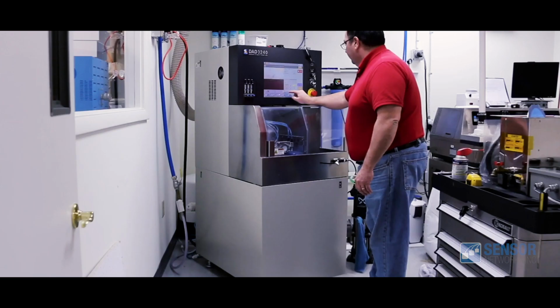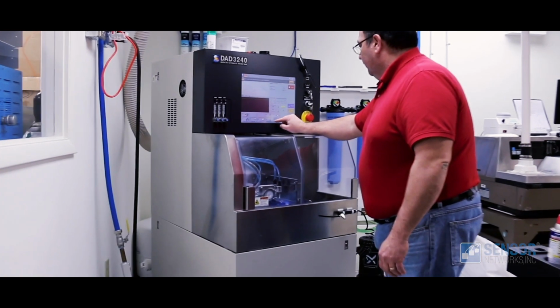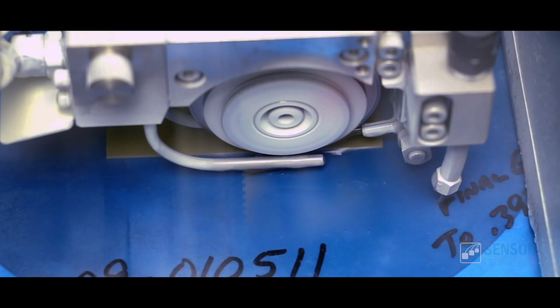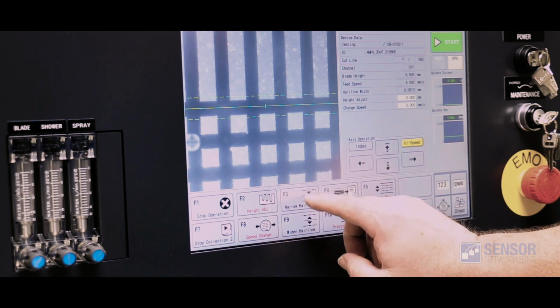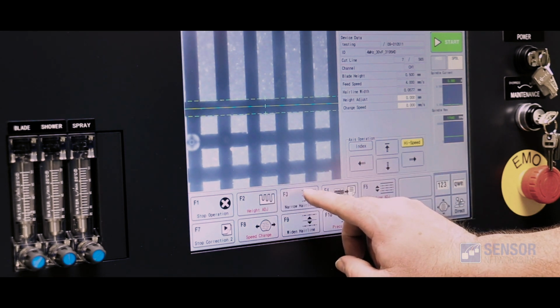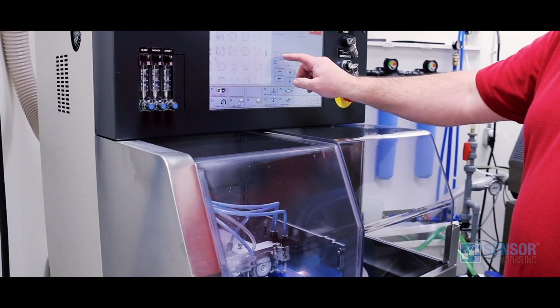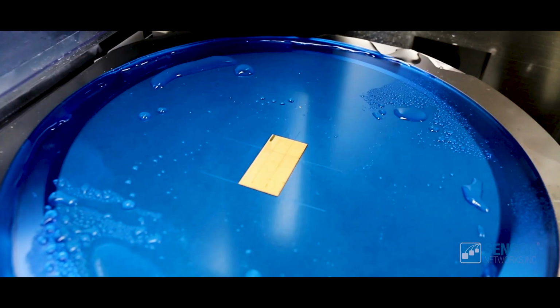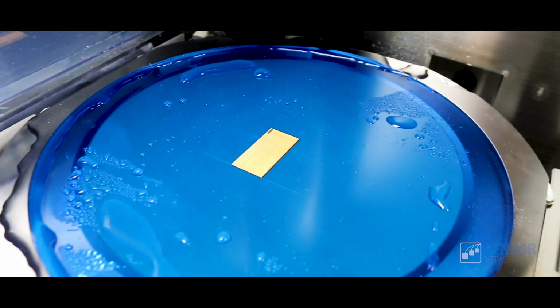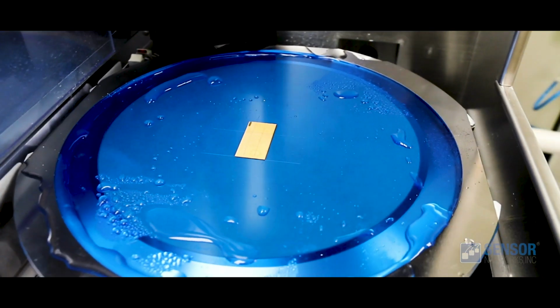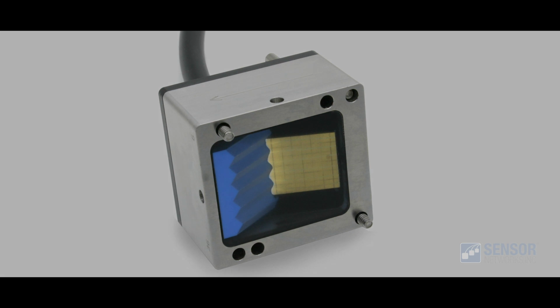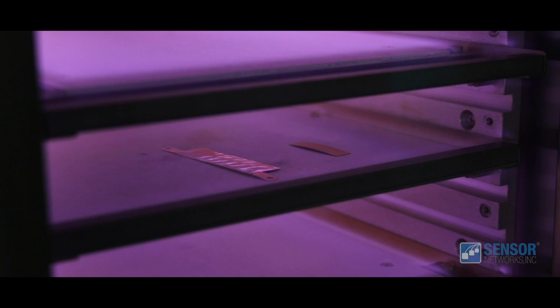At the heart of the phased array is the piezo composite ceramic. The ceramic is diced into many individual posts, which are backfilled with a polymer, ground to proper thickness, and plated. The ceramic gets diced once more into the individual elements, from 8 to 128 elements, which create the acoustic stack of the array. Linear, matrix, and radially formatted arrays are all possible. When dicing is complete, the ceramic is specially cleaned before assembly.